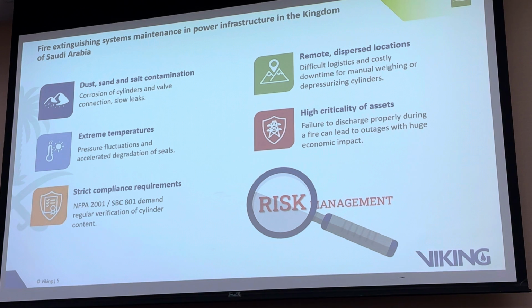Okay. So, why would we need to check contents, right? In these systems, we know they are very safe, they are very tight, right? Because there's a number of risks associated to any fire protection, Viking or anyone else, like dust, sand and salt contamination, for example, if you're close to the shore, like in Jeddah, like in Dammam, that can, over time, if they are exposed to harsh environments, that can one day induce leaks, right? Extreme temperatures, right? If there's sharp fluctuations or even very high temperatures, that can maybe at some point damage the seals over time.